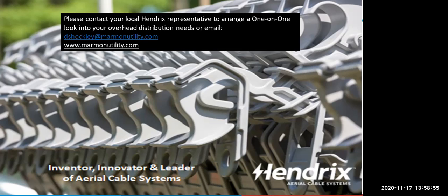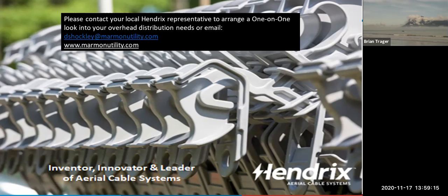Okay. Another question, when do you anticipate the 115 cable being commercially available? And can you give us an update on where we stand on that? I know we did a pilot project in Maine, so if you could tell us what you learned from that as well. Yes, thank you. Okay, so that pilot project was installed, I want to say late October in 2019. So after 1 year, we had been back several times with a company called Exacter doing partial discharge measurements and disturbance measurements.